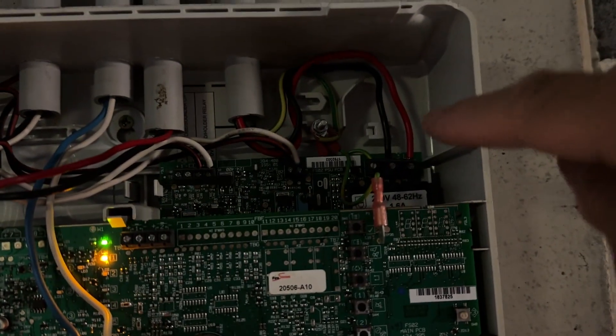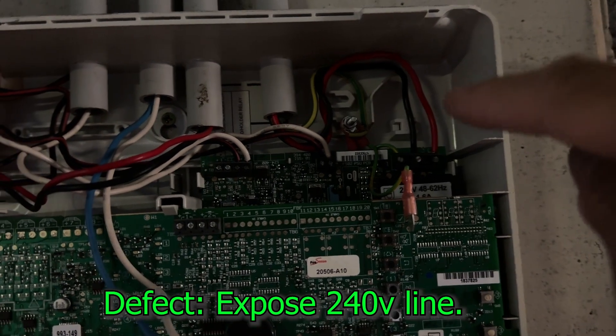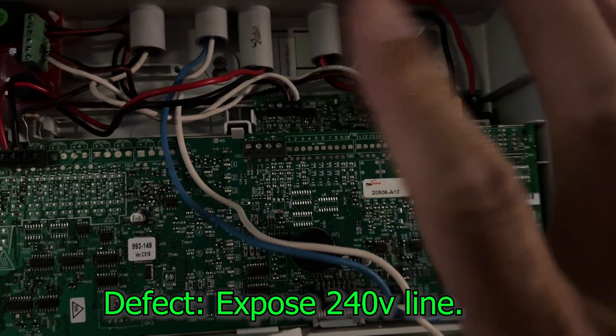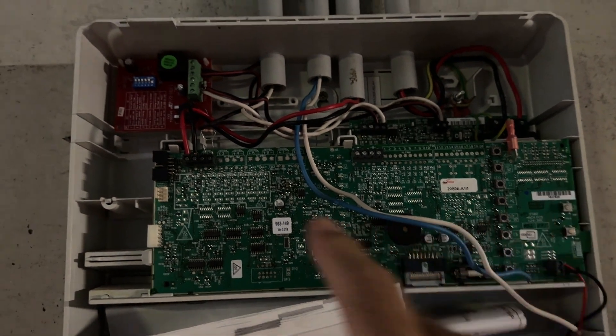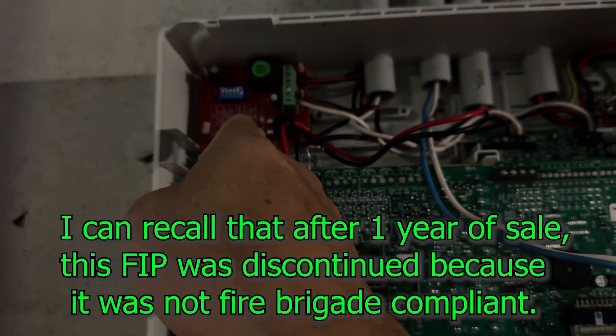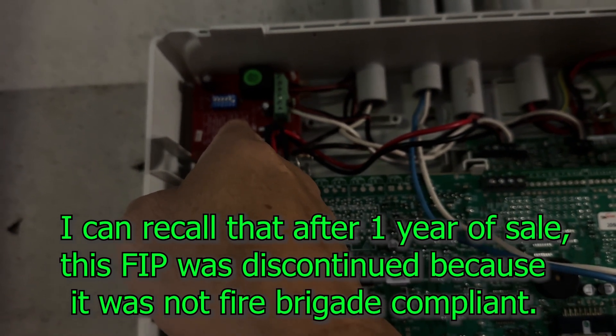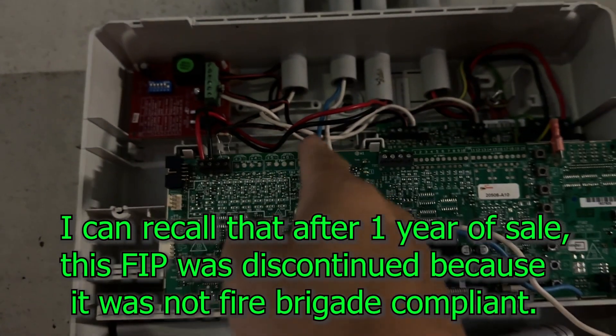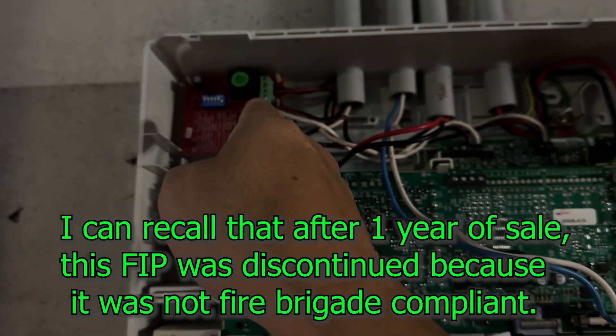The problem here is that that's 240 volts and it's exposed. That's not allowed, so that's why this panel is really not compliant. You have a delay, that is a magnet door holder trip delay. That means after an activation that will delay the drop.